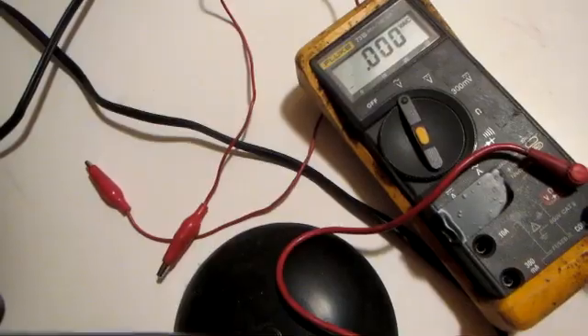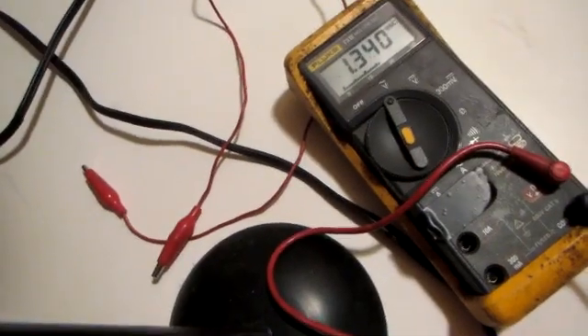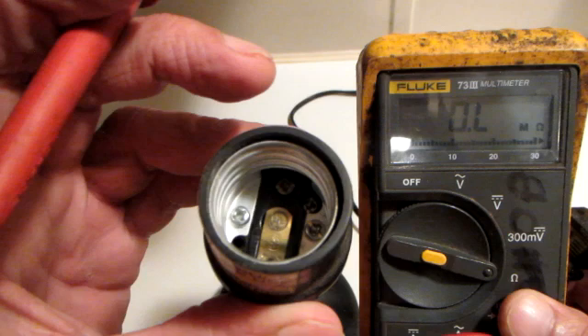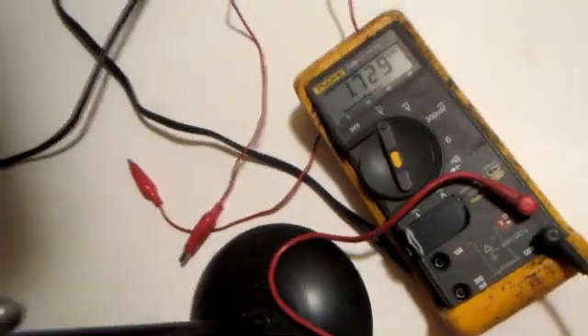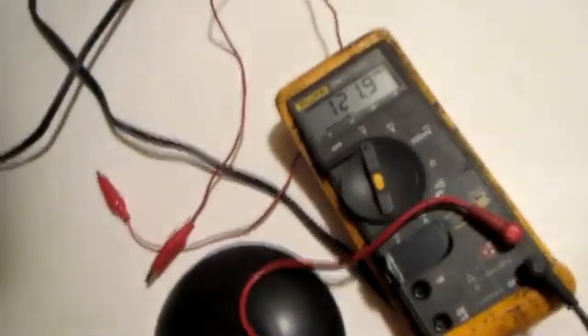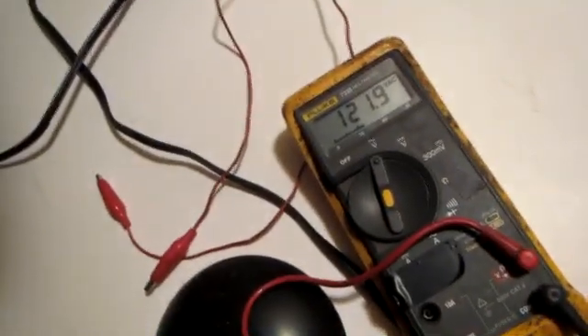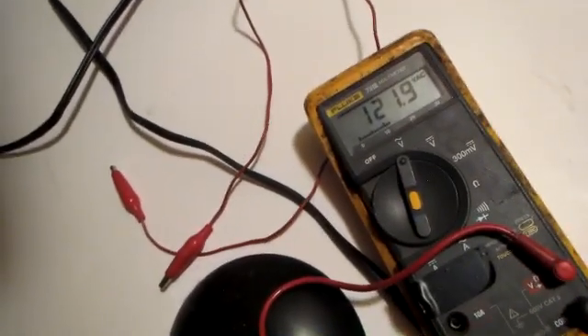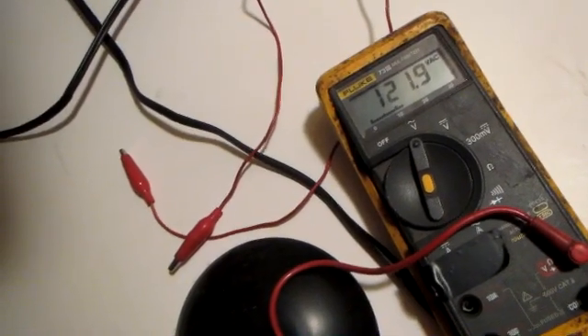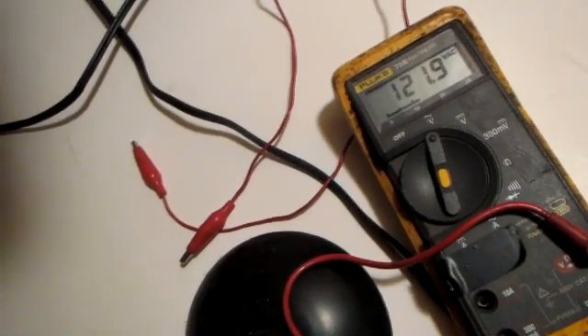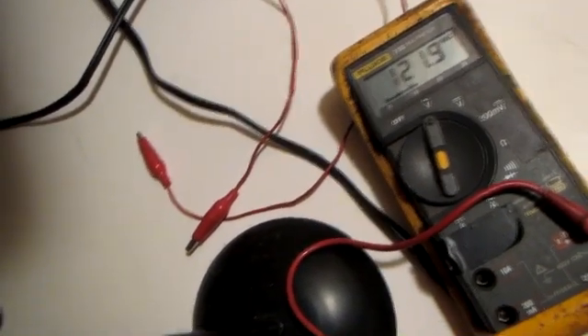Okay, now we need to take our meter lead and touch the center contact of our light socket. That's the contact on this light socket that is copper or brass in color, and you need to be real careful because if you are touching that brass contact and you touch the side walls, the threaded walls, you directly short out the circuit and you're going to have some arcing and sparking. There, we're reading 121.9 volts AC.